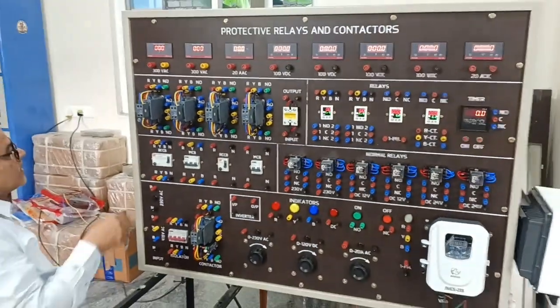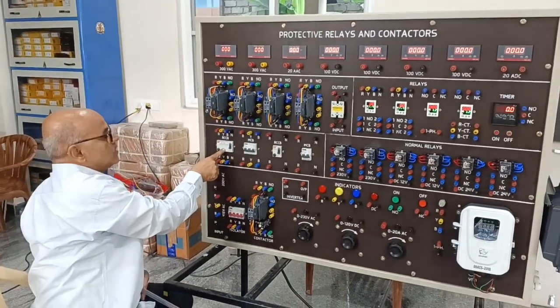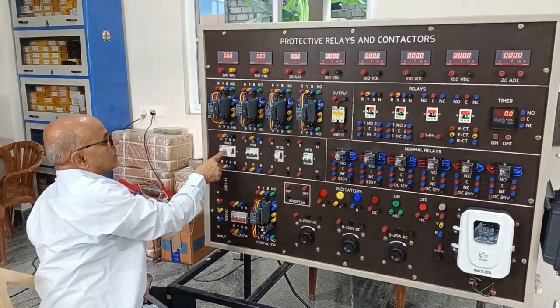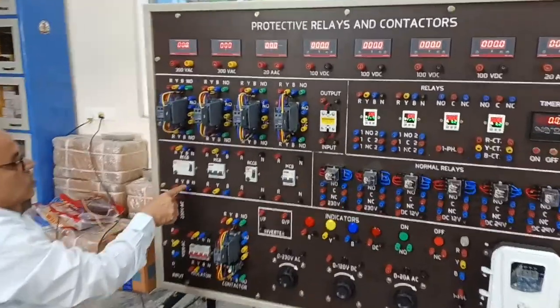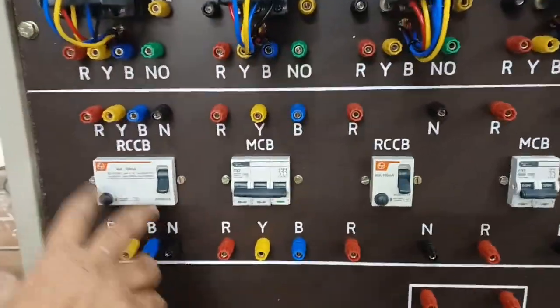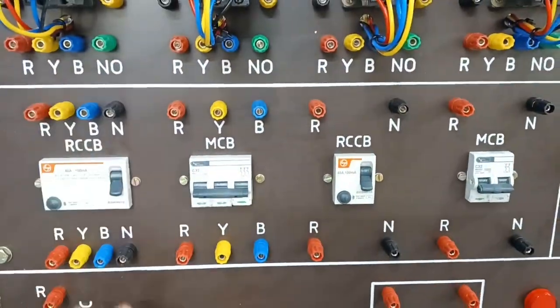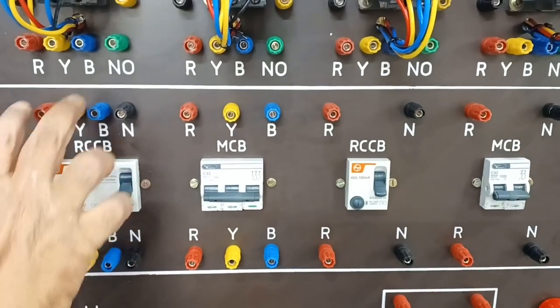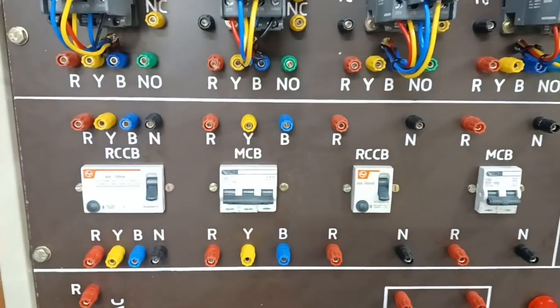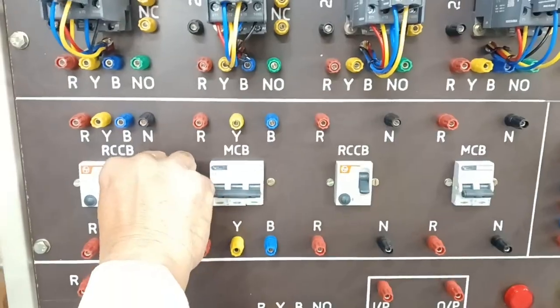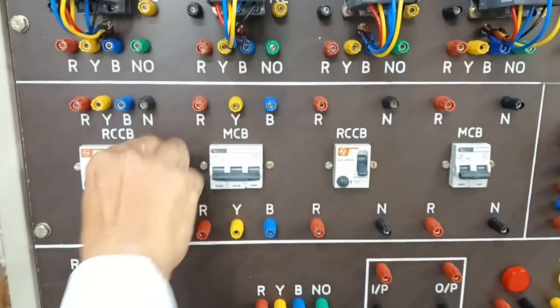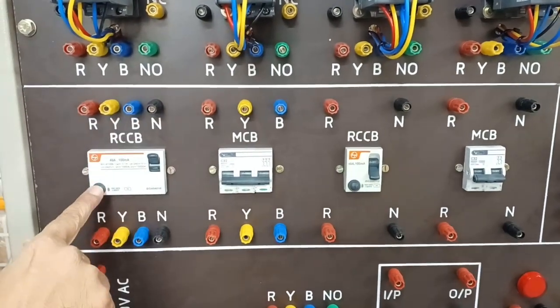And then here we have used one RCCB of 40 ampere current rating of 3 phase. This can be used for 3 phase. This is my input and this is output. You can give input 3 phase and you can take out a 3 phase output from here by using this. For any leakage current, this will get tripped and then you need to press this.